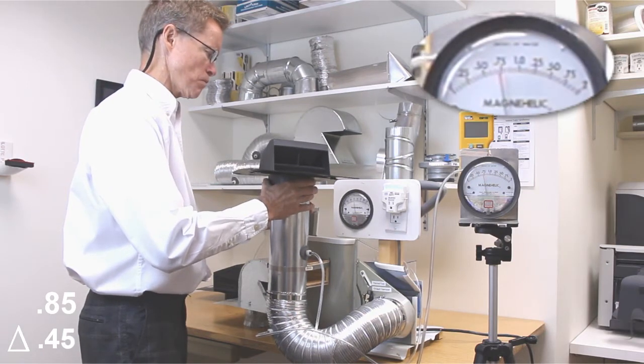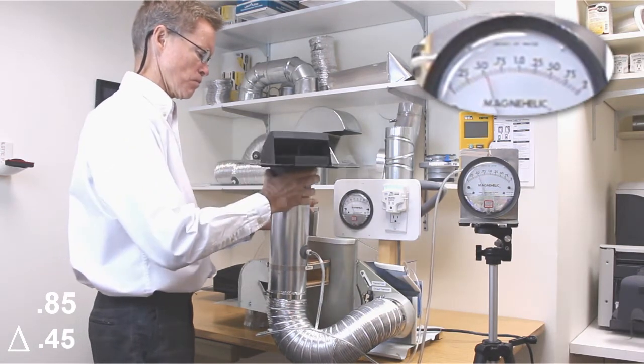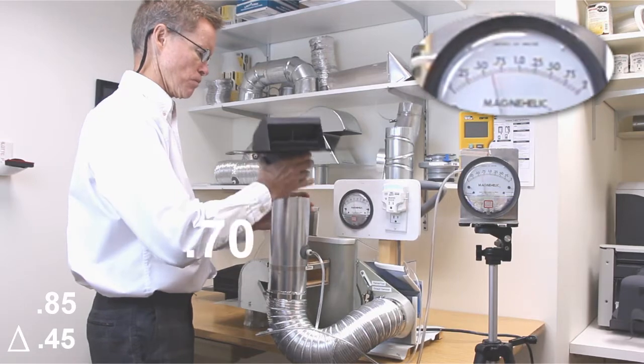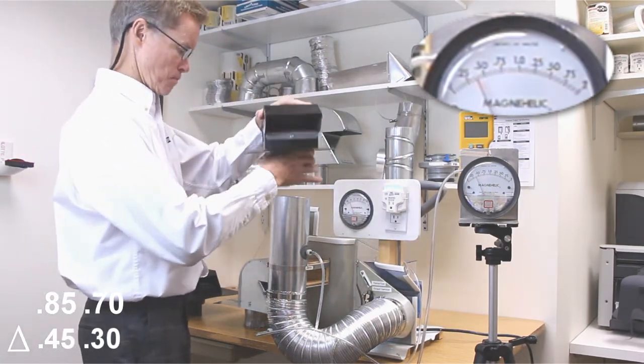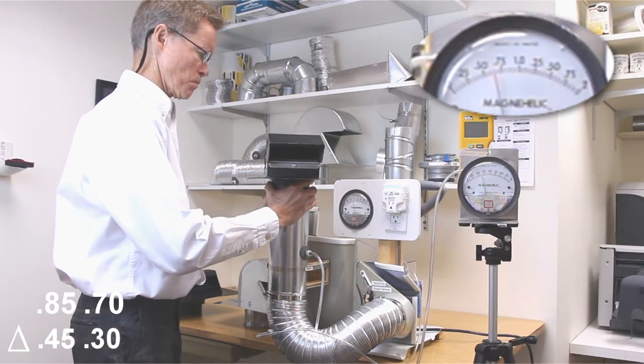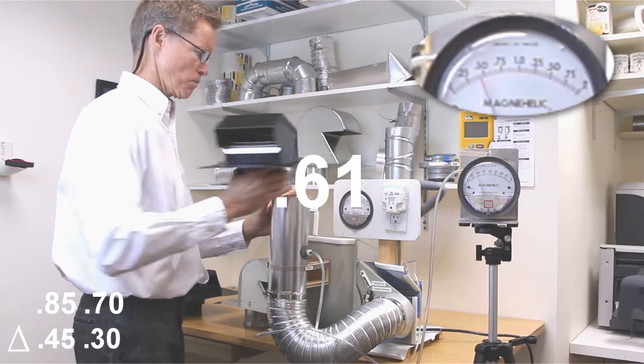A common plastic roof vent, again starting with 0.40 water column inch, rising to 0.70. A popular low profile vent, 0.40 water column inch to 0.61.